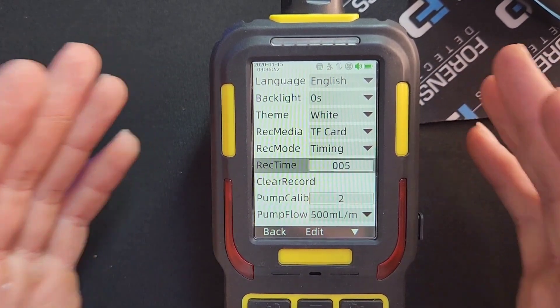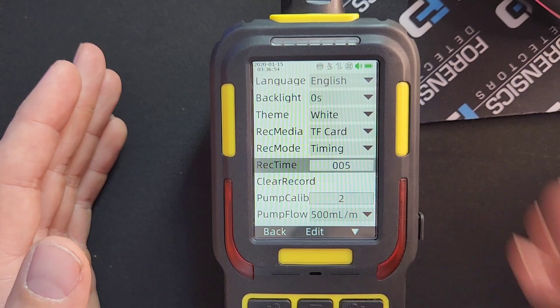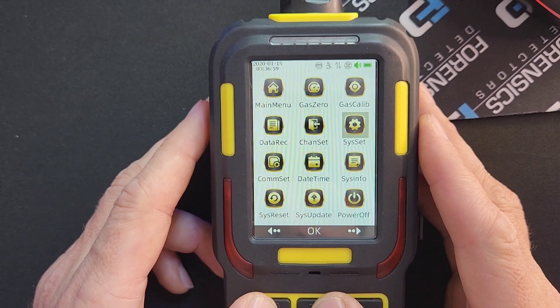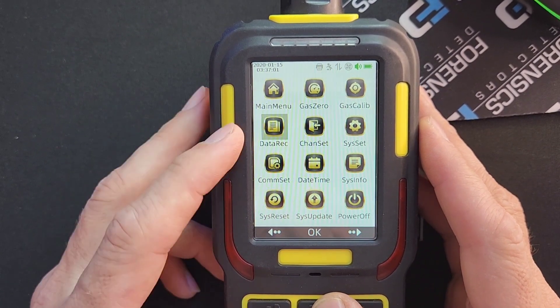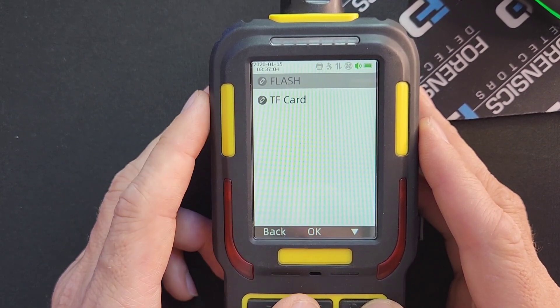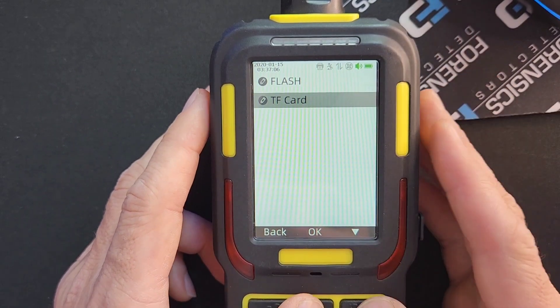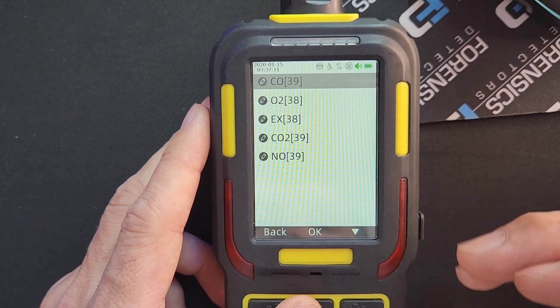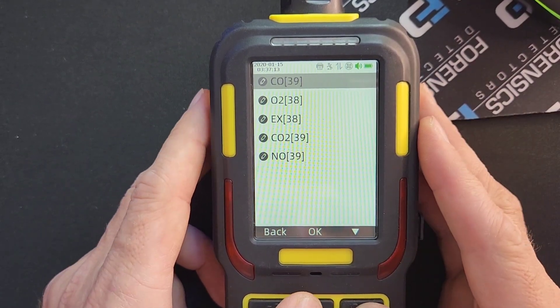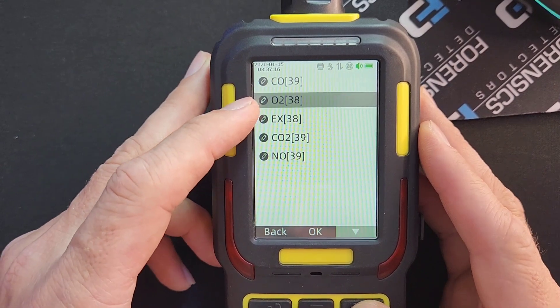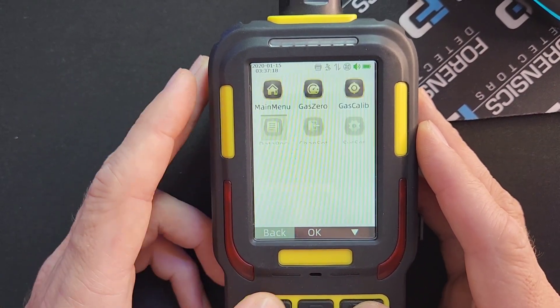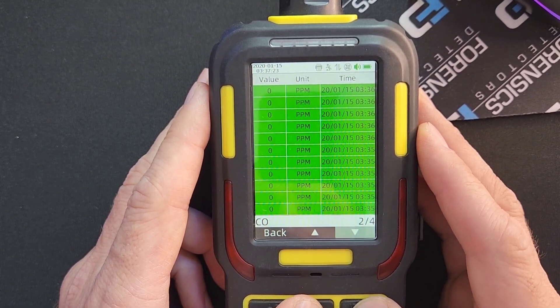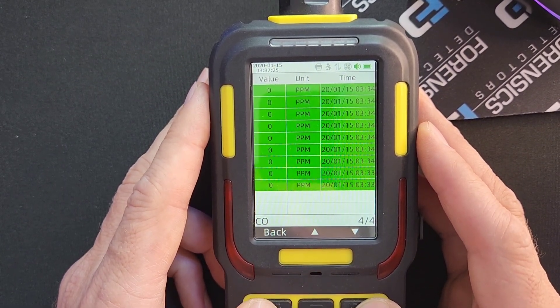We have set it up — quite straightforward and simple. To make sure it's actually recording, go back to Data Record, go down, confirm it's on the TF Card memory bank, press OK, and there you go — you can see in the square brackets how many data points have already been recorded for carbon monoxide, oxygen, EX, CO2, and NO.